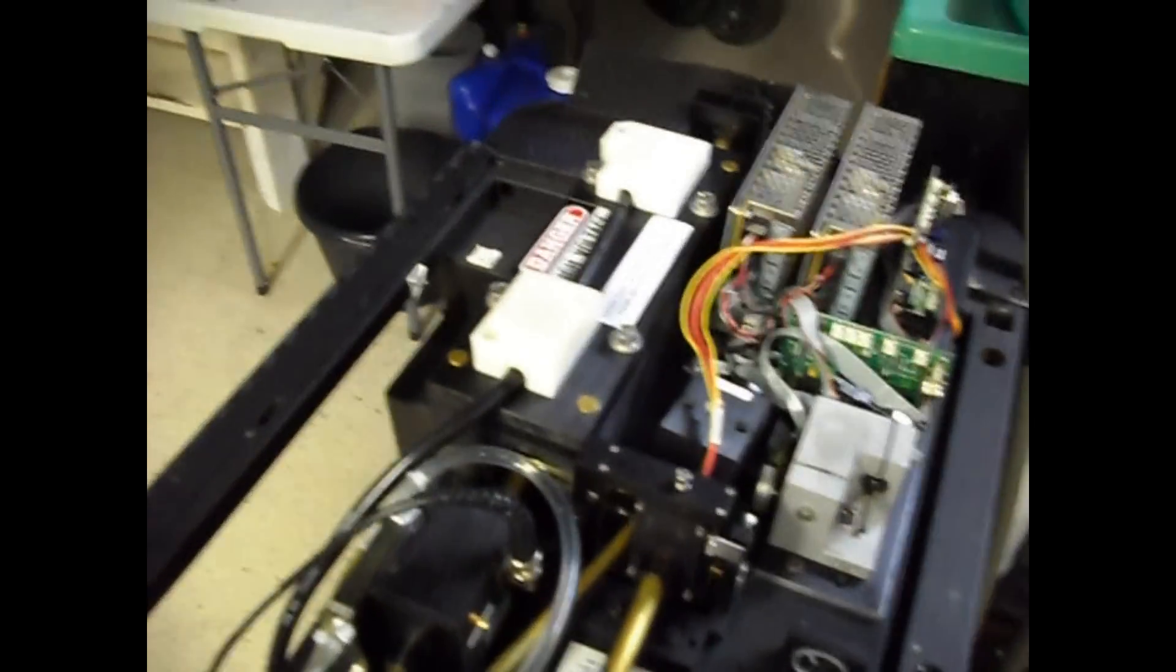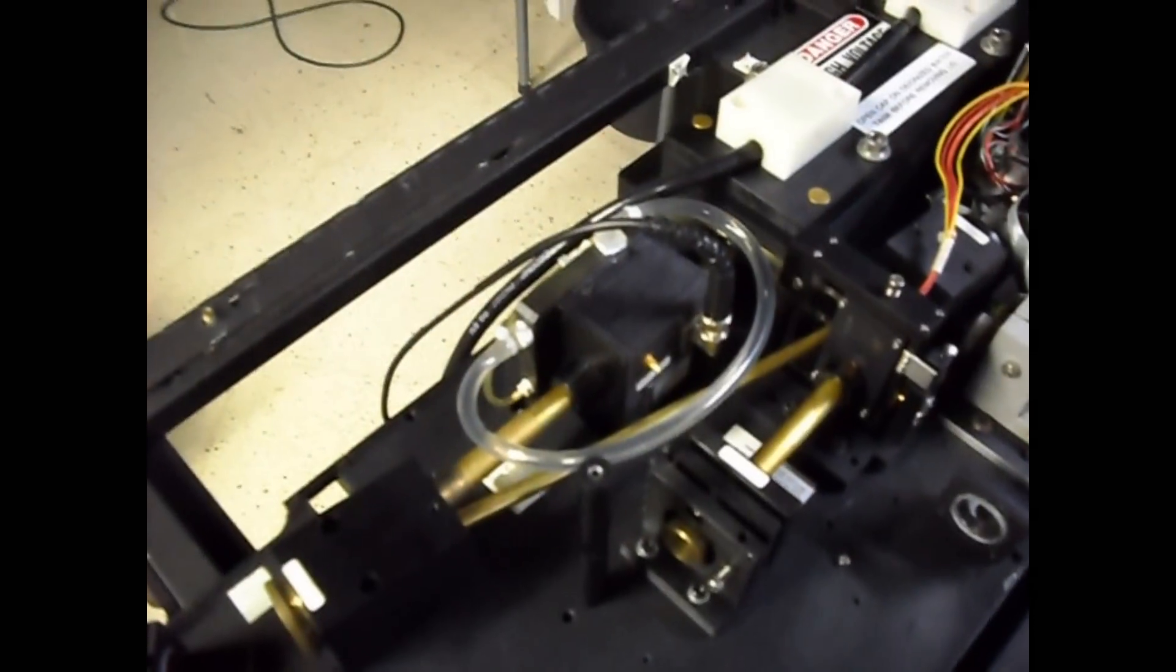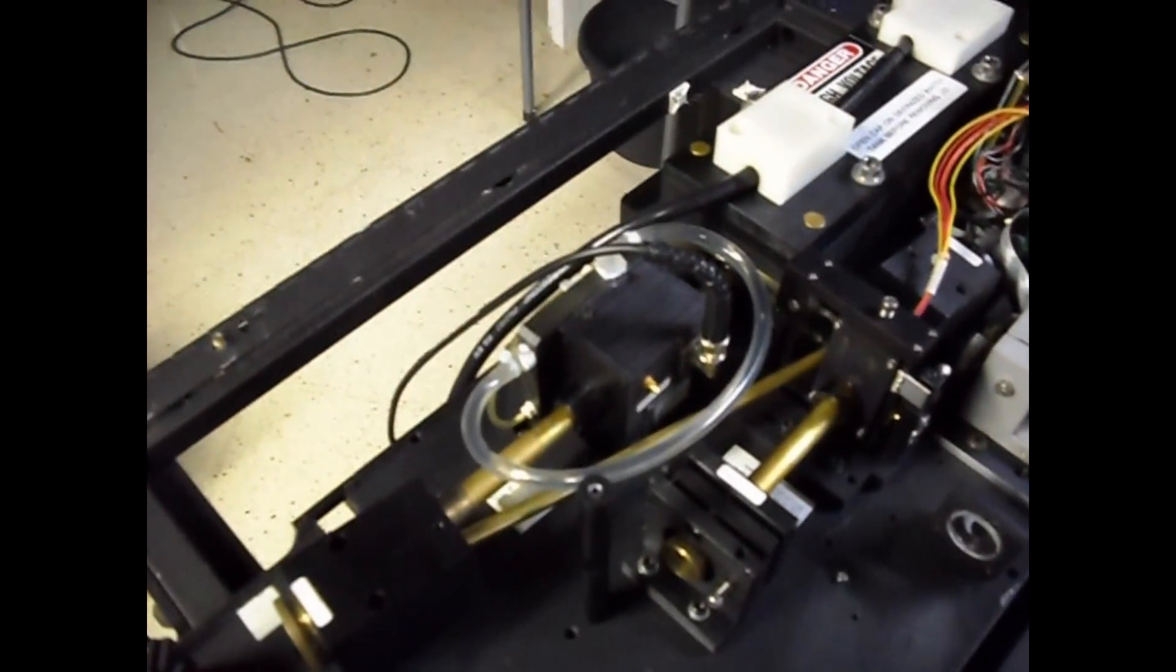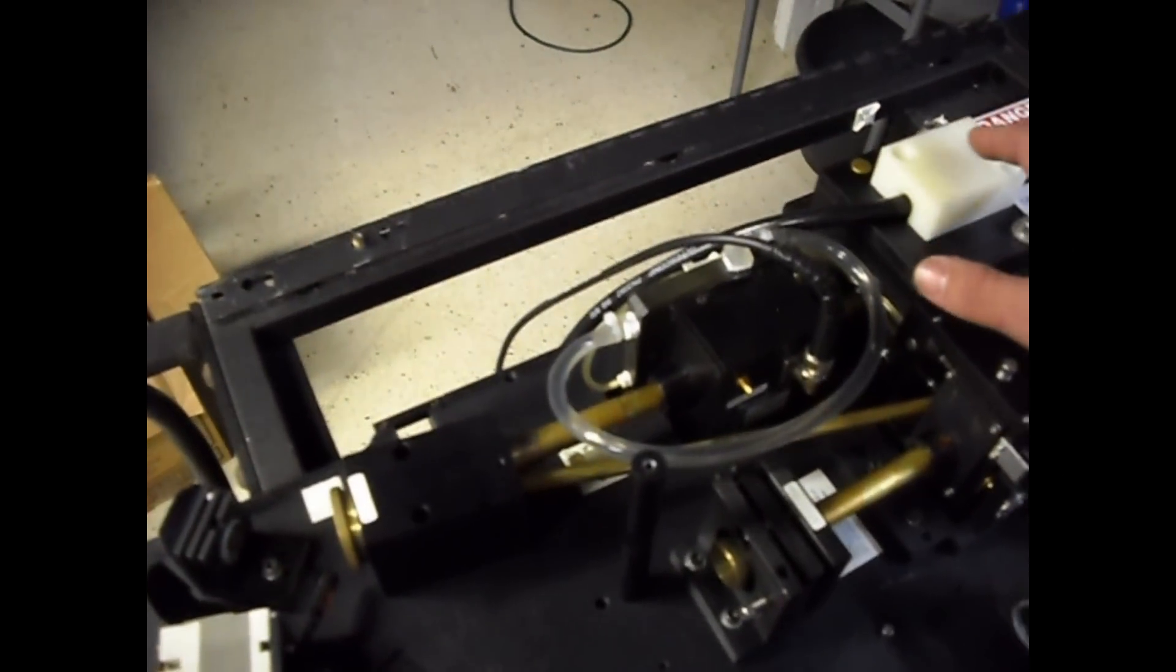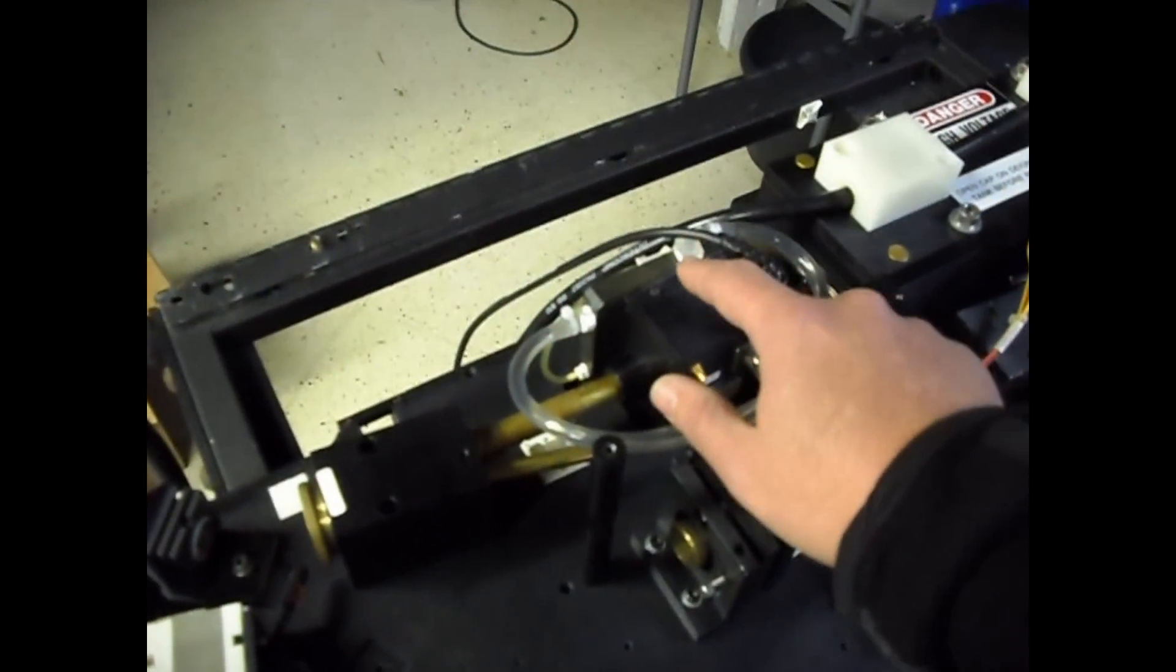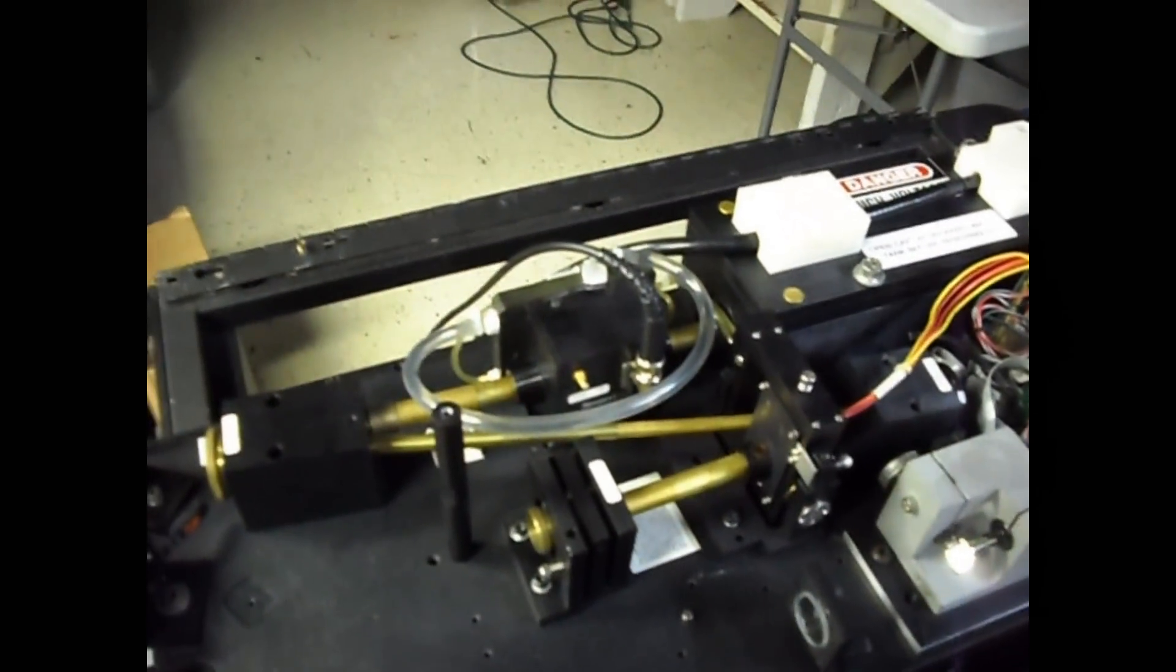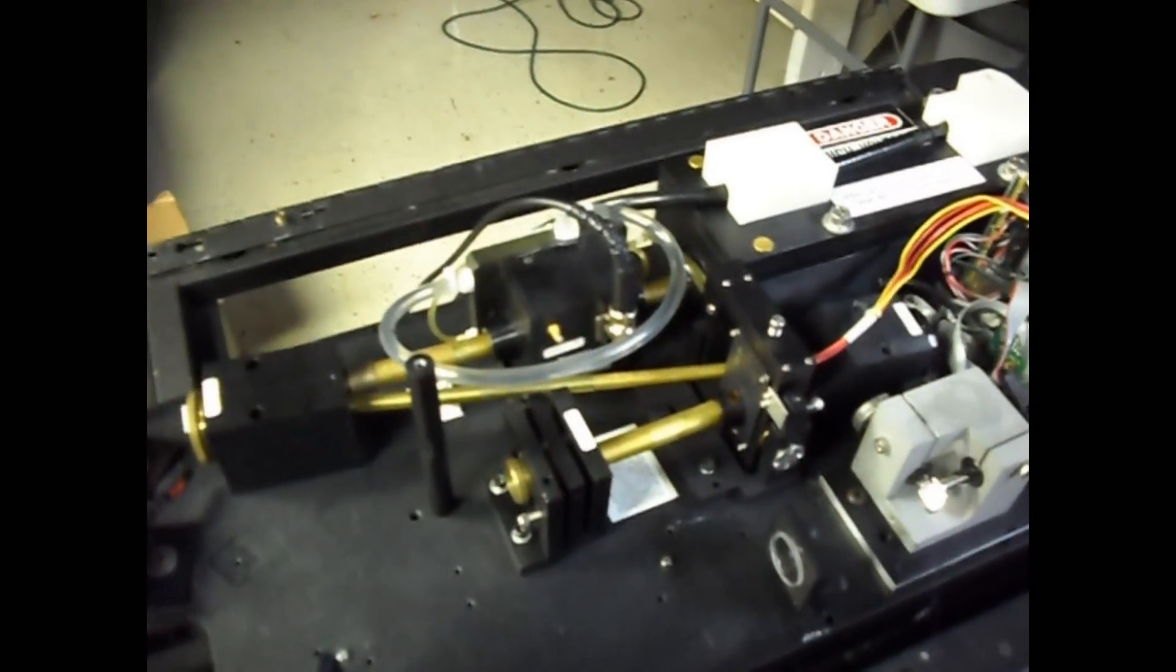So that's basically the top portion of the laser. And this right here is the Q-switch, quality switch. The best way to explain that to people that don't understand lasers is it's like a turbocharger for a laser. It basically chops the oscillation of the resonance of the cavity up into smaller portions. In doing so, it allows the YAG rod in here to energize and create what's called population inversion to a peak output, and then basically fires that oscillation. It's actually like a high-speed chopper, and it creates very powerful pulses and spikes of energy in the form of laser light to amplify the amount of power that's being fed to the KTP.